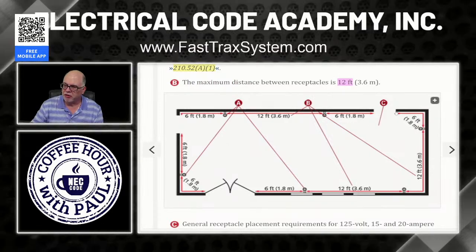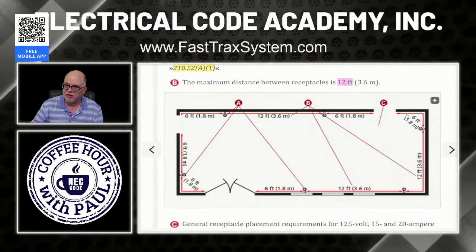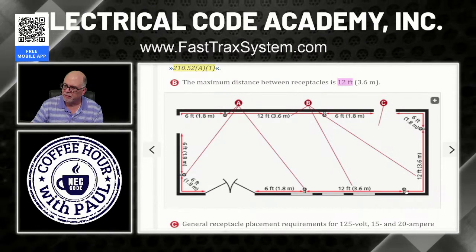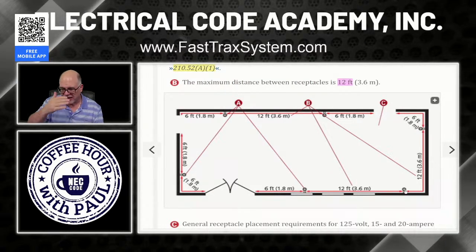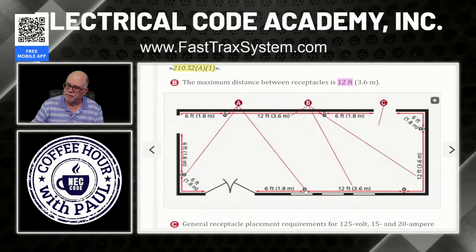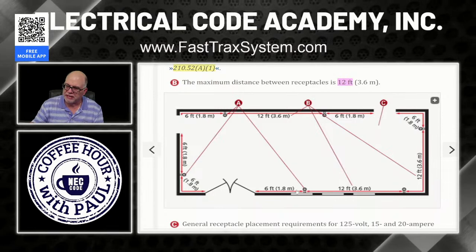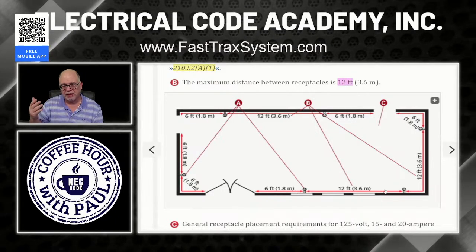Okay? So here's the break. You've got to have one within 6 feet. And there it is right here. And then you can go up to 12 feet. Don't have to go to 12 feet. You could go to 8 feet. You could go to 9 feet, but you could go all the way up to 12 feet. And you put a receptacle right here. And then you go another 12 feet, put a receptacle. And as long as that one here is within 6 feet of the end of this opening, of this break in the wall, then that's all you would need. And you're done. Okay.